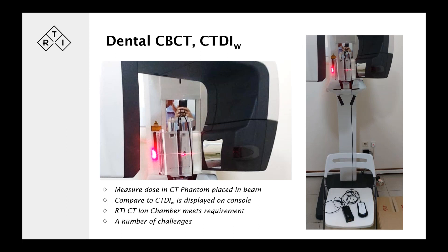To measure the CTDI weighted in a dental CBCT — which is often presented on the console as a value to be tested and tracked — you need to mount a CT phantom, place it in the beam (typically a head phantom), make an exposure, and compare that CTDI weighted value to the value on the console. We have an ion chamber that handles that, but there are a number of challenges when performing a CTDI measurement in a dental CBCT machine — one being finding a holder for the phantom to place it where it needs to be.